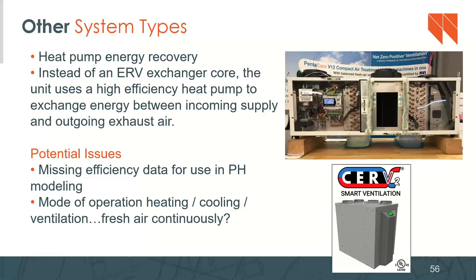Those demand controls are used pretty often in commercial applications, especially in terms of those systems detecting amounts of CO2 and turning on or ramping up, that sort of thing. So there might be something there in terms of moving that into the residential, into our homes and apartments. But the big takeaway here, not an ERV, not an HRV, you just need to look into this technology and see if it's right for your design. Again, for PHIUS, where we've heard the Minotair system was, PHIUS allowed that to happen in, I think, a multifamily building.